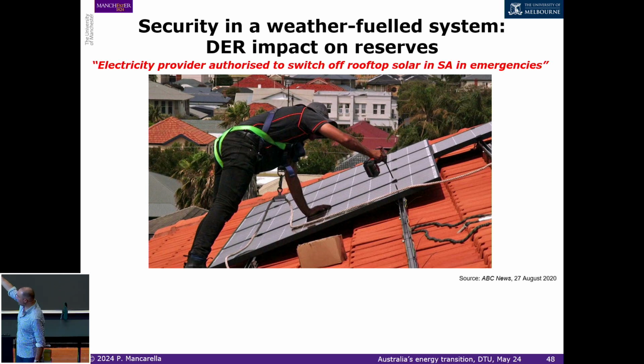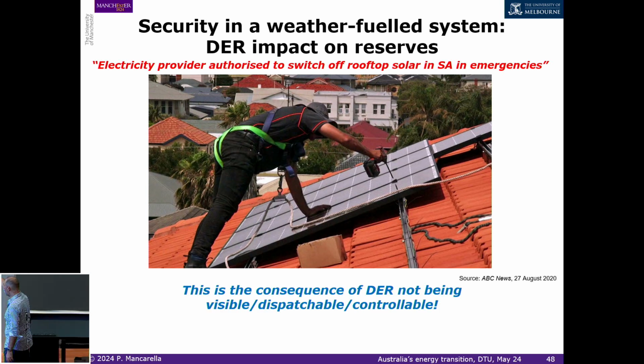So at some point, the system operator was not able to provide system security because the risk of losing distributed energy was so big. They said, okay, I can't do this, you need to switch off rooftop PV because the risk of tripping is so big that I cannot protect the system against that. This was particularly when South Australia was running as an island because there was maintenance on the interconnector. Again, this is just the consequence of DER not really being visible and dispatchable.